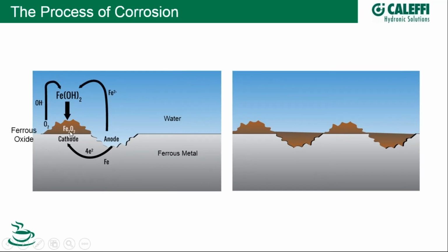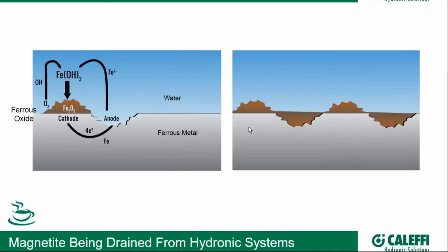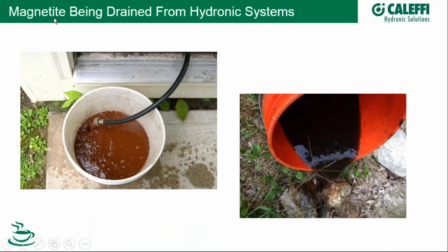But the upshot of it is ferrous oxide gets created. And we're looking at a very microscopic level right here. You wouldn't even be able to see this with the human eye, but we've blown it up to show you chemically what's happening. And it wouldn't happen only in one spot. It would be happening concurrently, uniformly across the metal, generating a surface that would look rough microscopically, but from a distance might still look smooth. But if you have an ongoing process of oxygen in your system, then the corrosion continues unimpeded and begins to slough off and starts to float around. That corrosion or debris is called ferrous oxide, and it exists in a hydronic system typically in the form of magnetite.